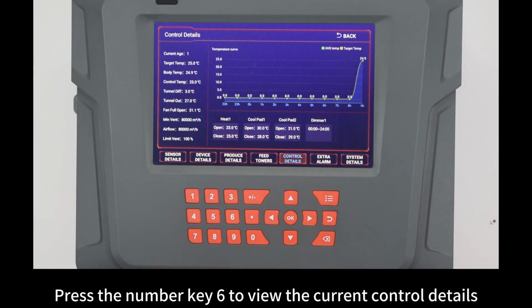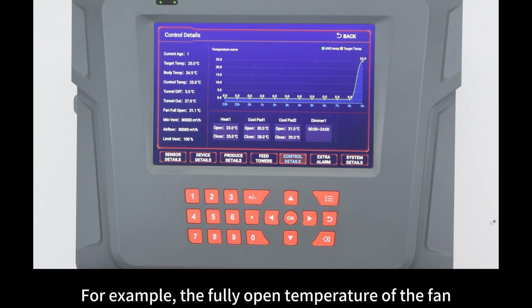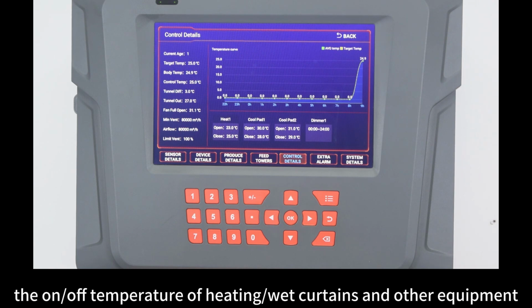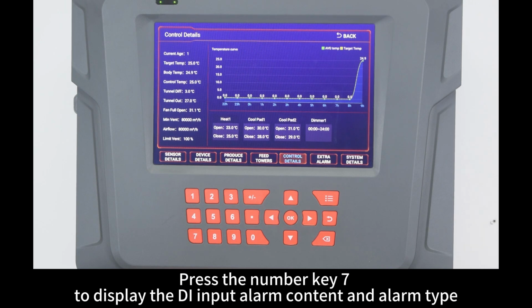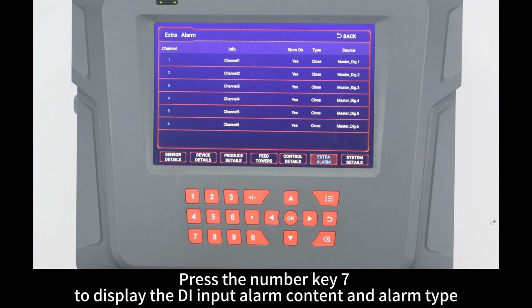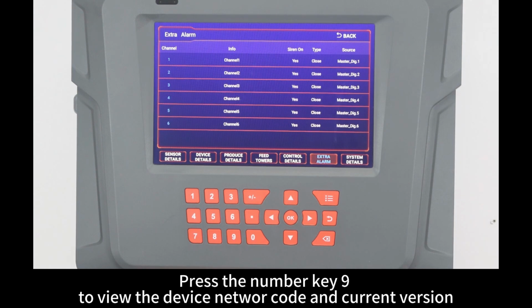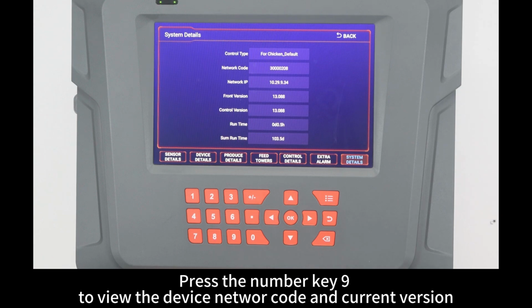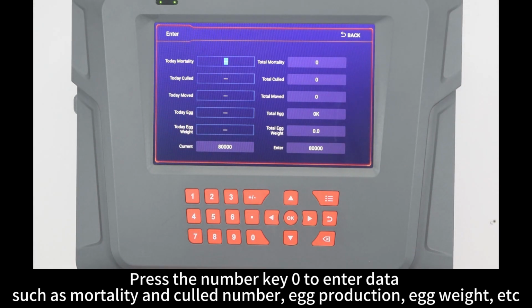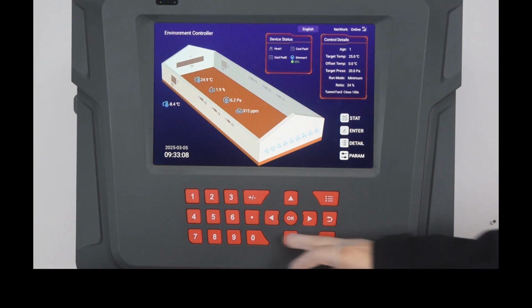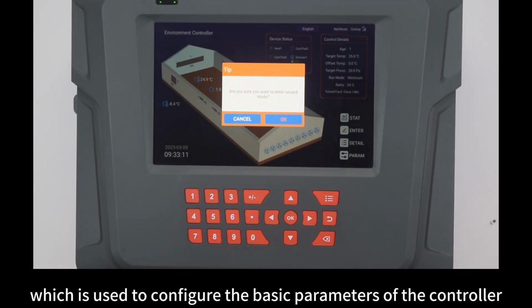Press the number key 6 to view the current control details. For example, the fully open temperature of the fan, the on/off temperature of heating, wet curtains, and other equipment. Press the number key 7 to display the DI input alarm content and alarm type. Press the number key 9 to view the device network code and current version. Press the number key 0 to enter data, such as mortality and cull number, egg production, egg weight, etc. Press the plus key to switch languages. Click the point key to enter the setup wizard, which is used to configure the basic parameters of the controller.